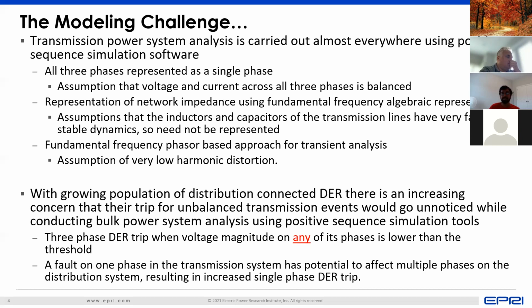So we don't have a time-varying transient of the voltage. And we assume that everything is around fundamental frequency, in the sense that if you have a 60 Hertz system, we assume that most of the disturbances would be around 5 Hertz around 60 Hertz, so that you can have a phasor-based approach for representing this behavior. All of this is done to aid the computational challenge and to ensure that we have a much more robust and fast simulation environment so that we can study very large systems.